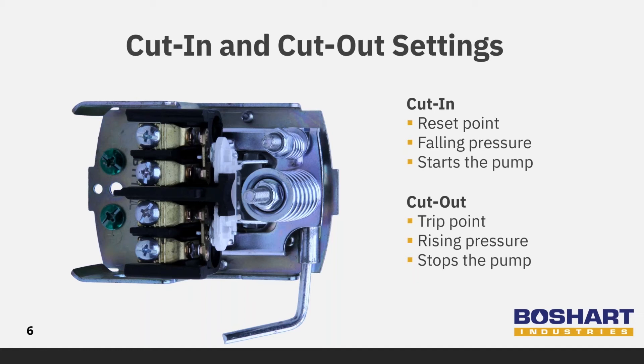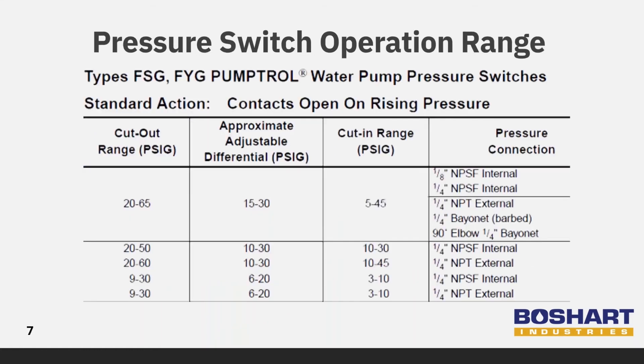Turn the nut on the large spring clockwise to raise both the cut-in and cut-out pressure. Turn the nut counterclockwise to lower both the cut-in and cut-out pressure settings. For accuracy and to optimize the life of the switch, the cut-in and cut-out set points should be in the middle of the operating pressure range. Following the presentation, this technical sheet outlining the minimum and maximum cut-in and cut-out ranges will be available for download for your reference.